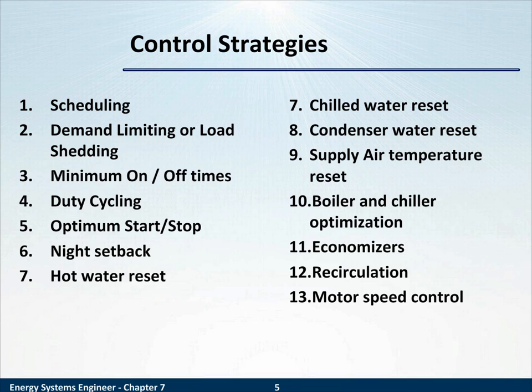The next idea of night setback is a very common practice, and it just allows the temperature when people aren't there to set back 6 to 8 degrees. So in the summertime, you let it get 6 to 8 degrees warmer. In the wintertime, you let it get 6 to 8 degrees cooler. And it's often used in conjunction with other control strategies like optimum start-stop.